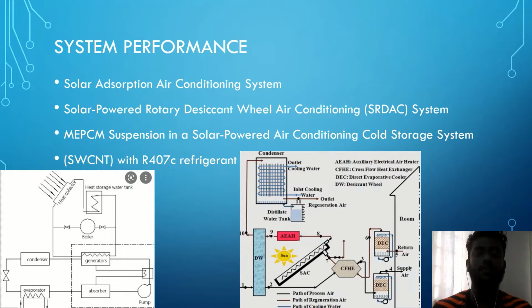First, the solar adsorption air conditioning system. It is environmentally friendly since it uses solar energy to drive adsorption with clean water. There is potential for solar adsorption cooling applications in office buildings in tropical regions. Silica gel and zeolite-water combinations are used in prototypes. According to performance data, the solar portion of the solar adsorption system is as high as 63% under average temperature and relative humidity.